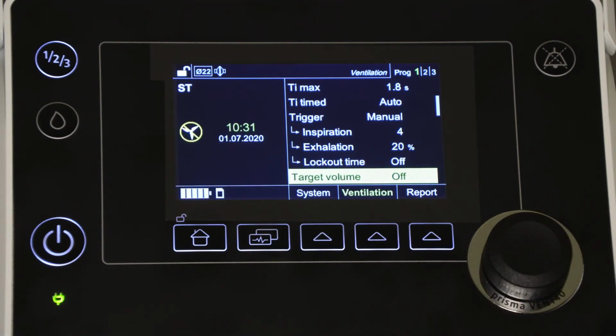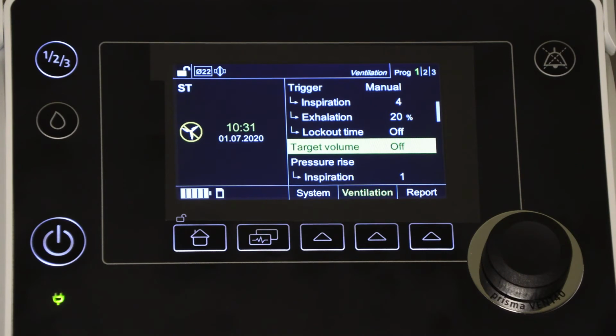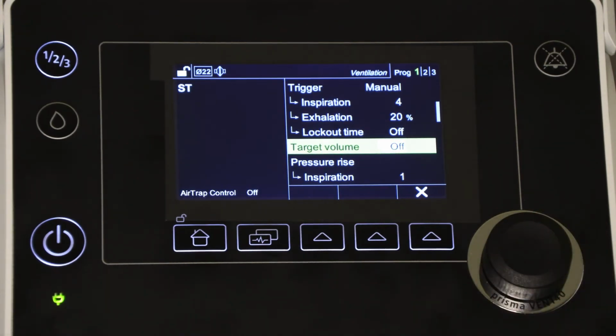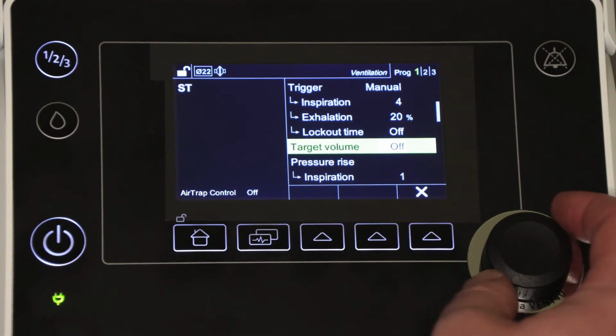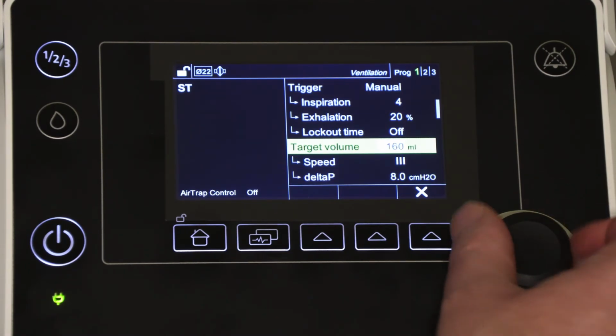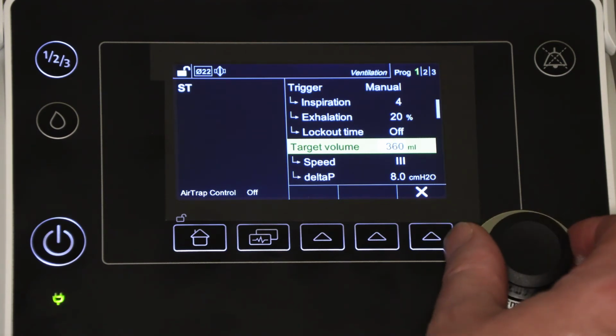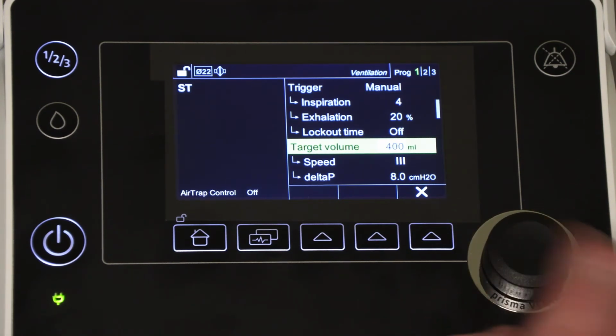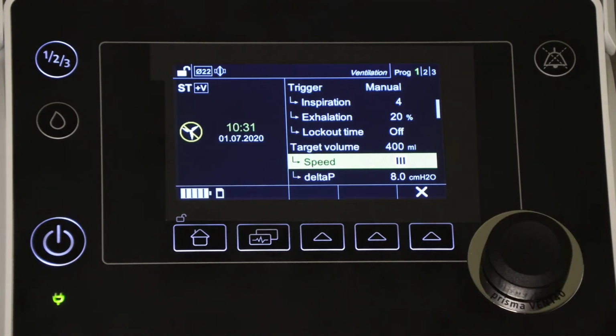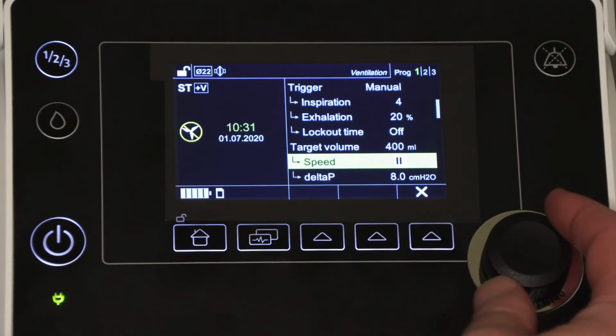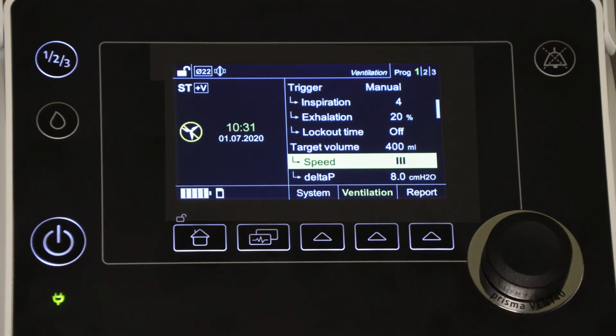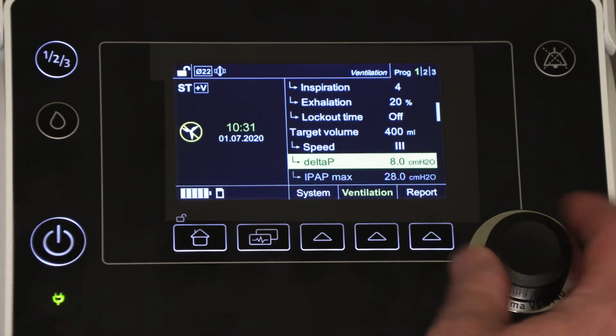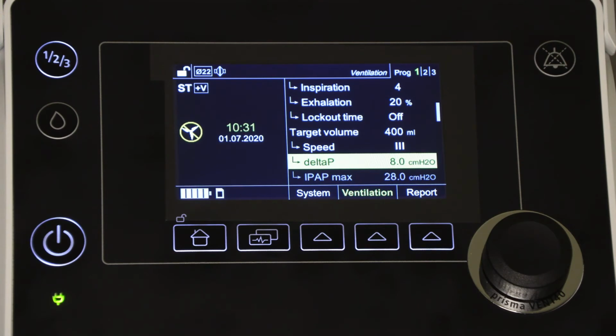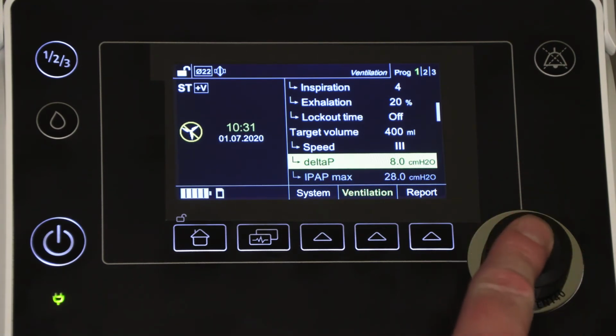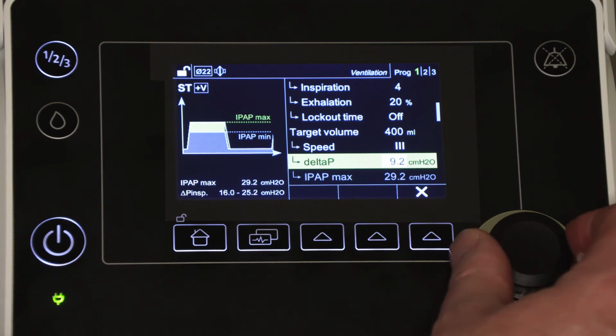Target volume can be set to react by increasing the set IPAP up to a preset max IPAP in the event that the patient's volume drops below a set target. To use this feature, first set a target that you don't want the patient's volume to fall below. Then set the reaction speed. Step 1 is the slowest reaction time and step 3 is the fastest. Next, set a delta P, which is the amount you want to allow the ventilator to increase its IPAP pressure by if this maneuver is required.